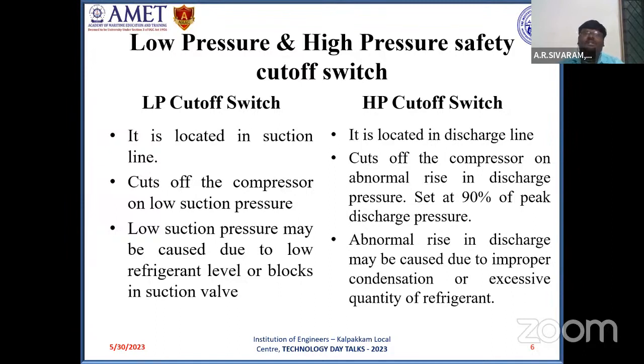So generally, when there is a possibility of low suction pressure, the level of refrigerant is low. We would have seen that on one fine day we set an indoor unit temperature of 20 degrees Celsius in a room, but the air conditioning system, after running for half an hour, may not give the desired 20 degrees Celsius that we set. That may be due to a low level of refrigerant, that is, a low volume of refrigerant in the system, which can result in low suction pressure. Apart from this, a block in the suction valve may also cause low suction pressure.